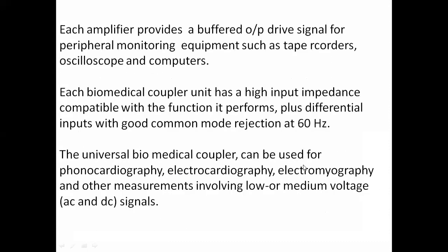Each amplifier provides a buffered output drive signal for peripheral monitoring equipment such as tape recorders, oscilloscopes, and computers. So it will also act as a buffer amplifier. The main purpose of a buffer amplifier is to provide high input impedance and low output impedance, and by that we can apply the total voltage to the peripheral monitoring equipment. Here the peripheral monitoring equipment means the tape recorders, oscilloscopes, and the computer display.